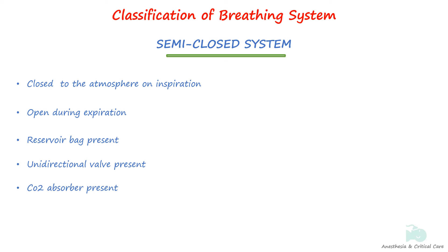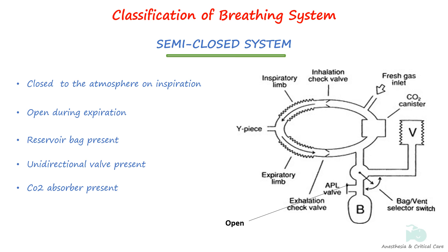In a semi-closed system, the patient's respiratory system is completely closed to the atmosphere on inspiration but partly or fully open to the atmosphere on exhalation, allowing carbon dioxide to be washed out. Semi-closed breathing systems have a reservoir breathing bag, partial re-breathing of exhaled gases, unidirectional valves, neutralization of carbon dioxide, and low fresh gas flows. These include circle systems with an APL valve that is at least partially open.